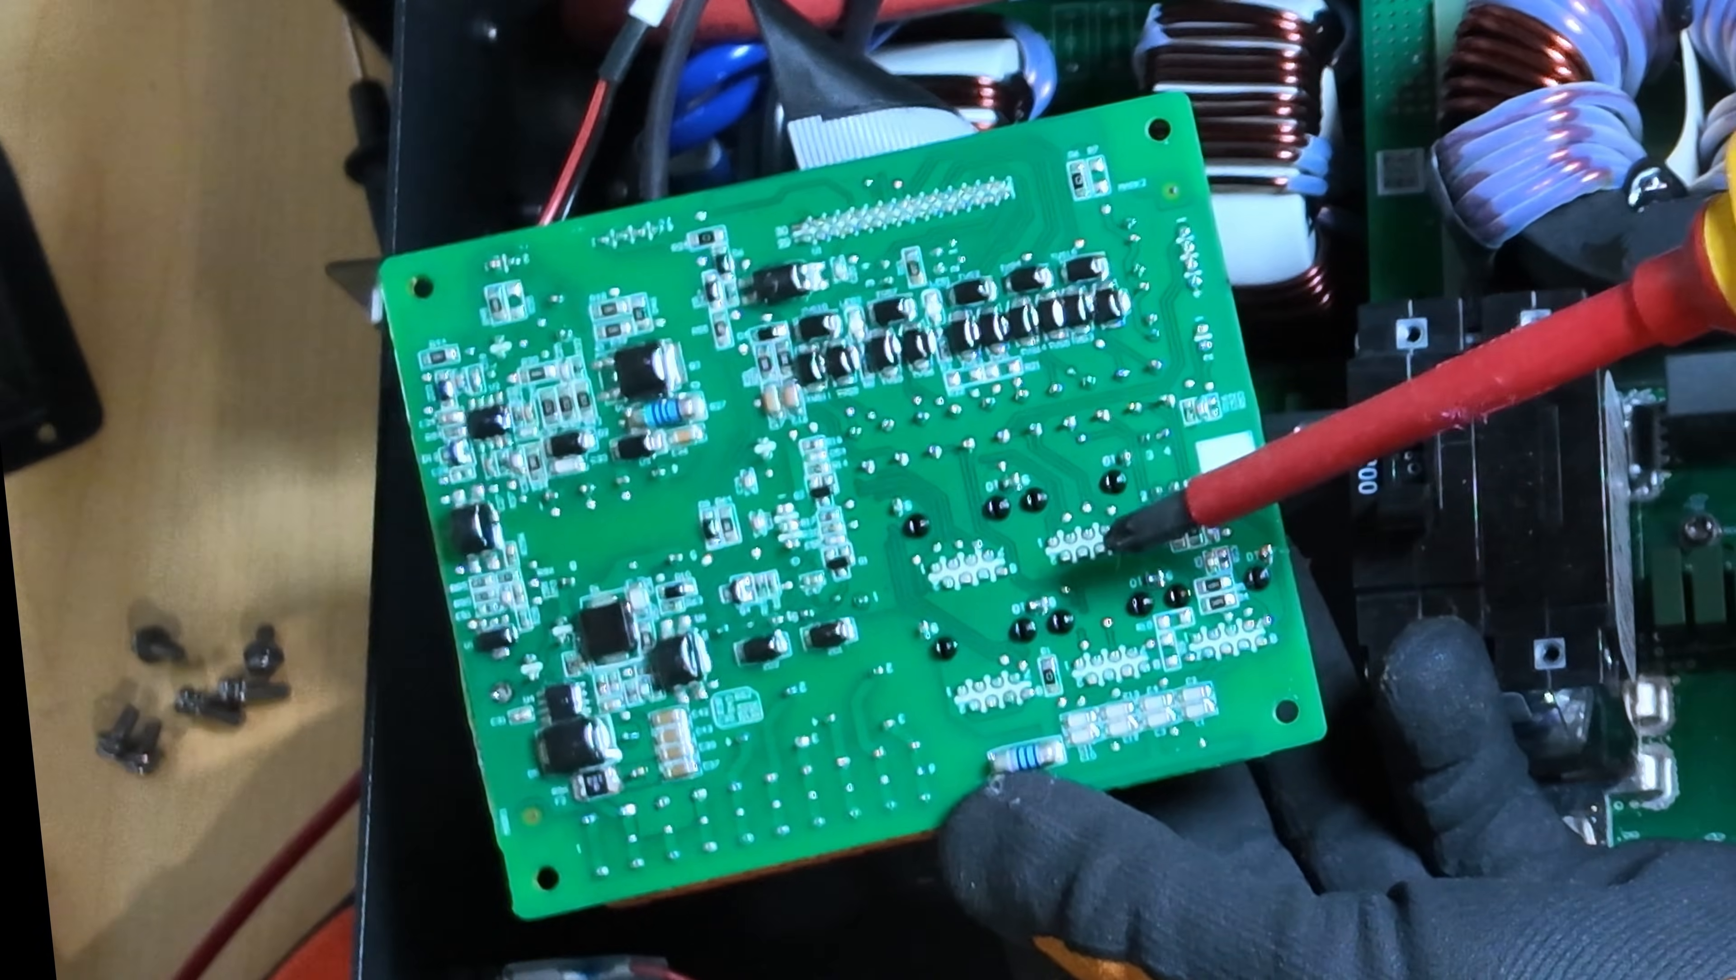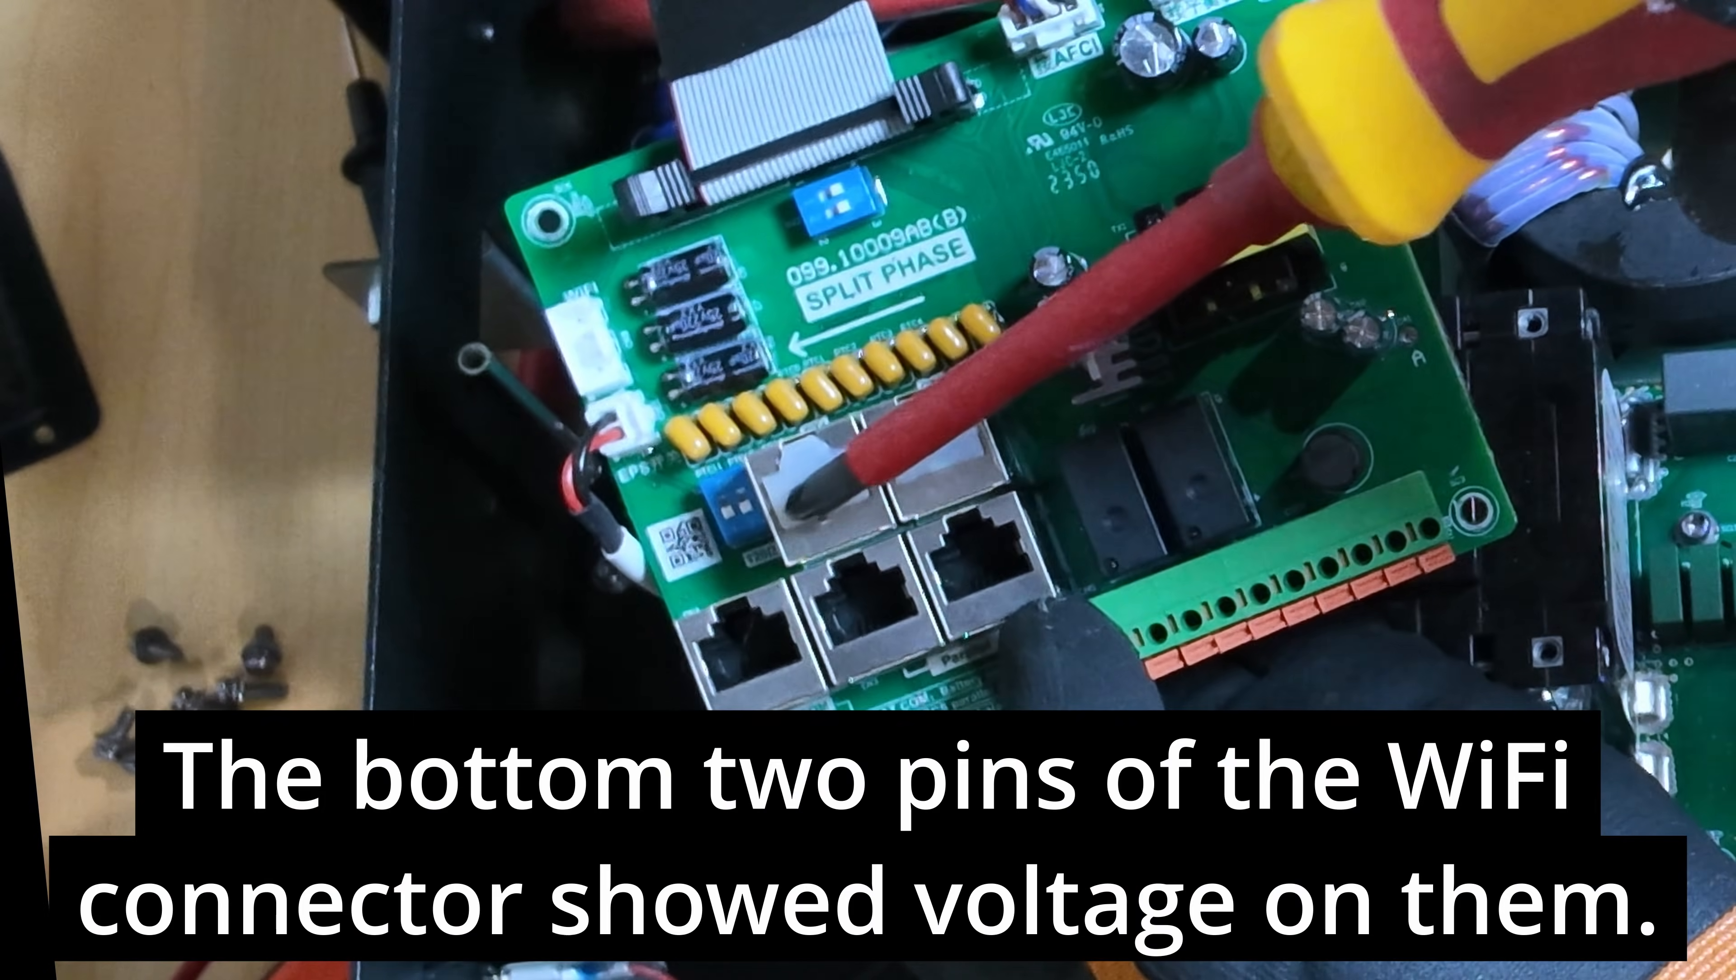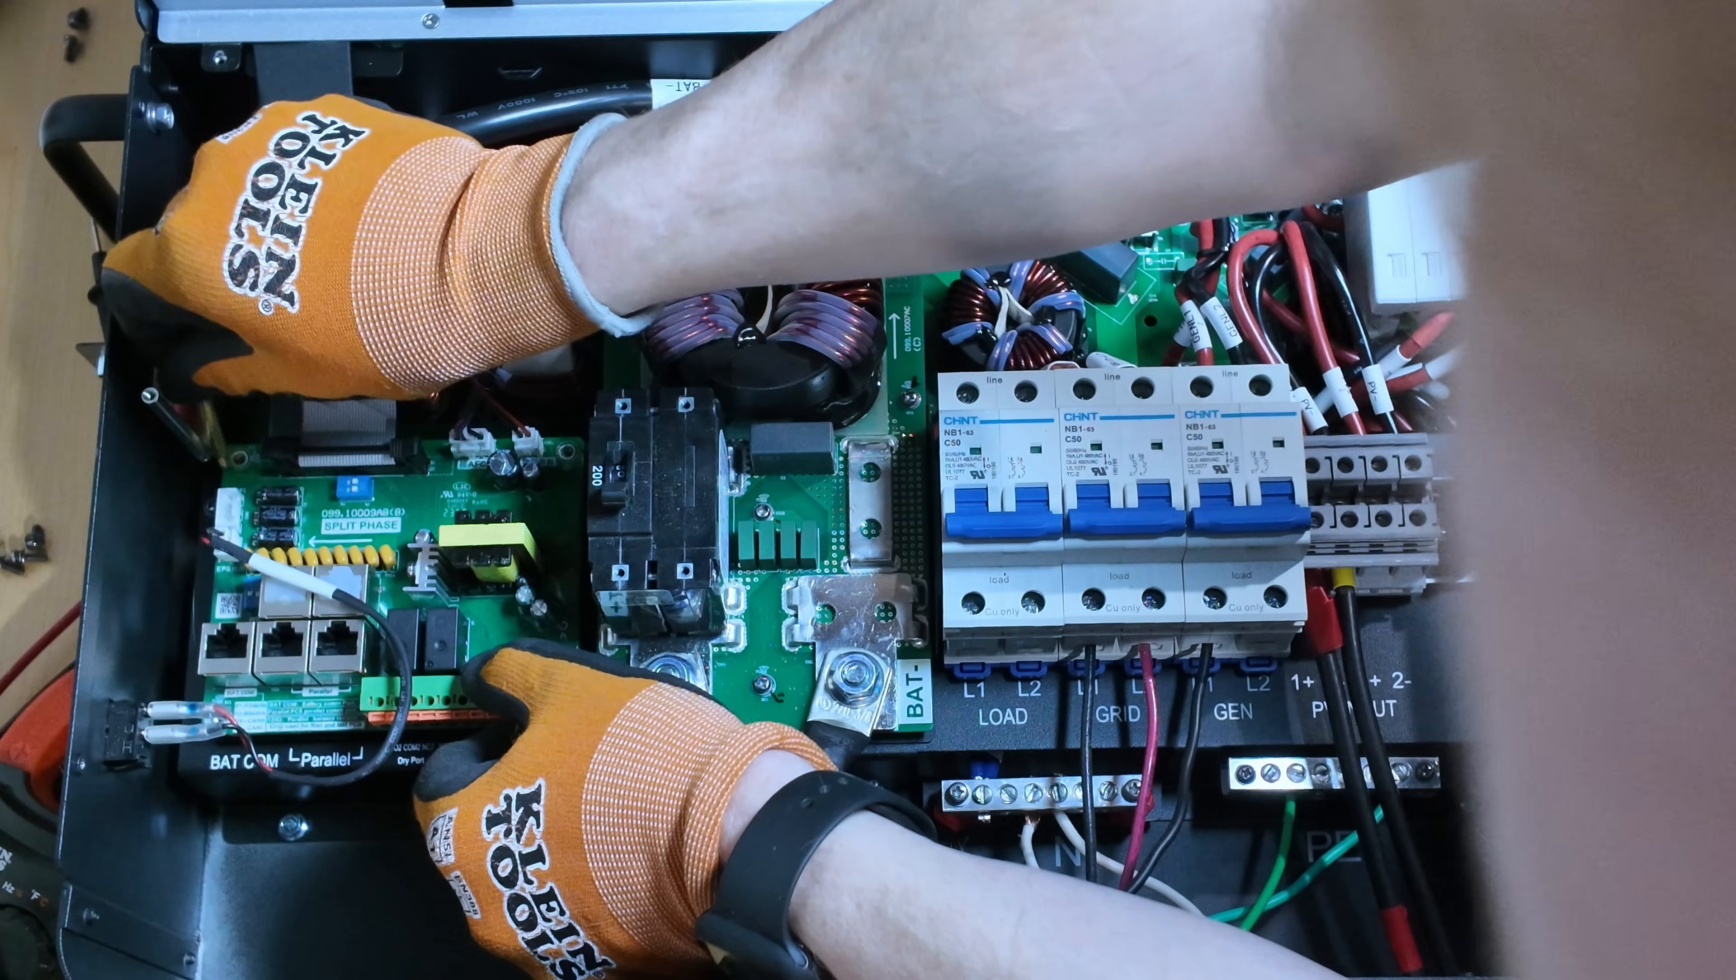Well, this set of terminals is actually the CT Connection 1. So I grabbed my meter and I double-checked. I toned out these top two pins, toned out to pins 7 and 8 on the CT1 port. And I'm in a very tight space right now, so I'm not going to repeat that toning. So we'll go and tighten these back down just so they're not moving.